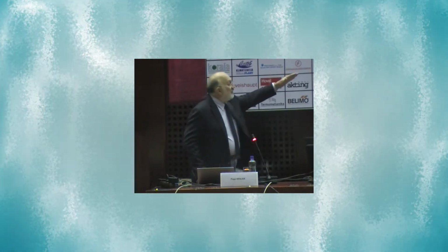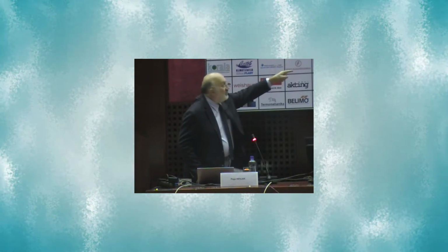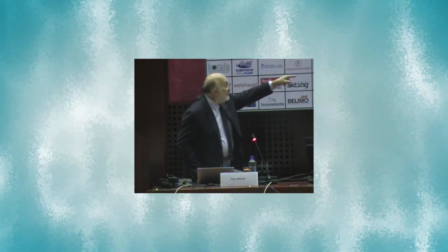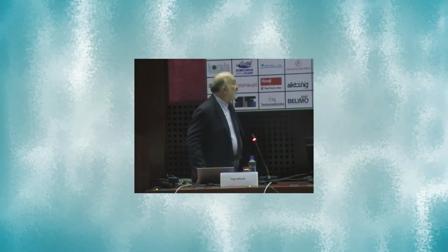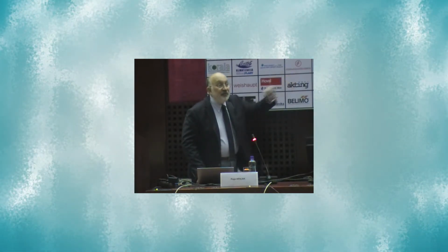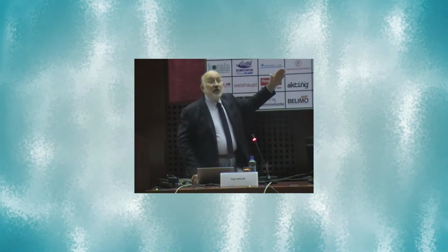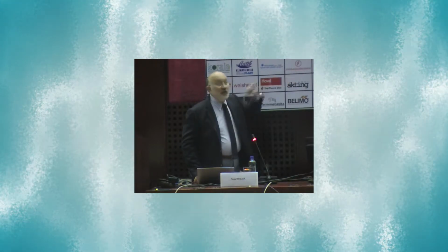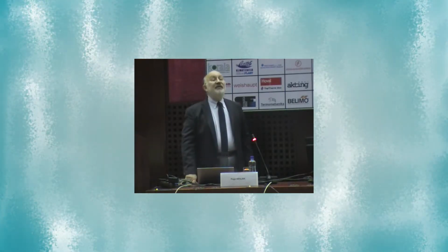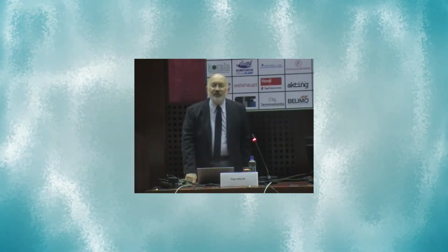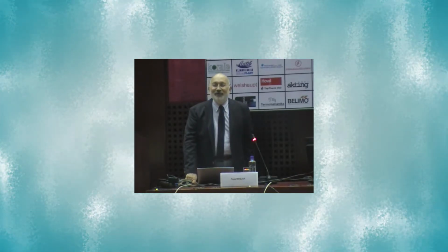What do we see on the left side? There is a pressure drop per meter length as a function of the vapor quality from liquid to vapor. We see as the vapor is generated, velocity goes up, and of course pressure drop goes up. This is kind of obvious here. Nevertheless, in all of these cases, pressure drops start to go down. Do you know why pressure drops start to go down?